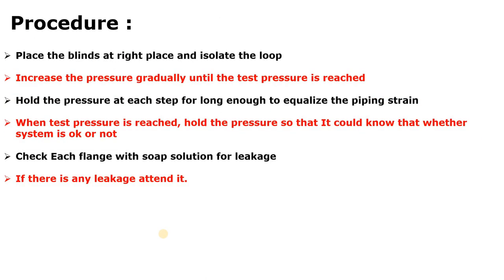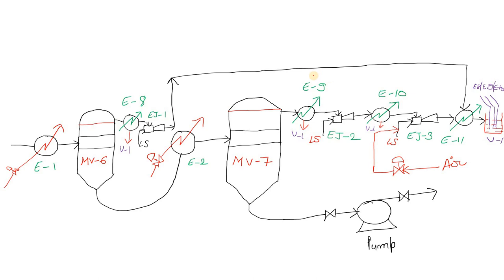Now, what is the procedure for the pneumatic test? First, place the blinds at the right place and isolate the loop. Here is a diagram — we have to perform the pneumatic test on this system which is a low pressure, i.e., vacuum section.